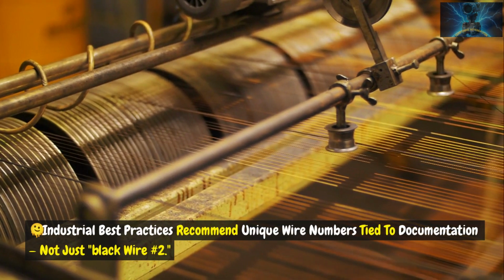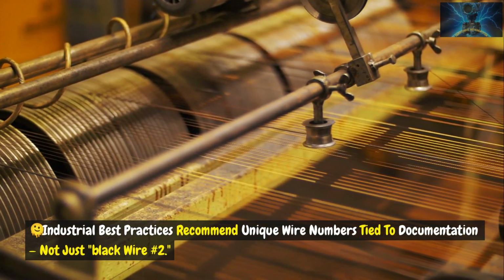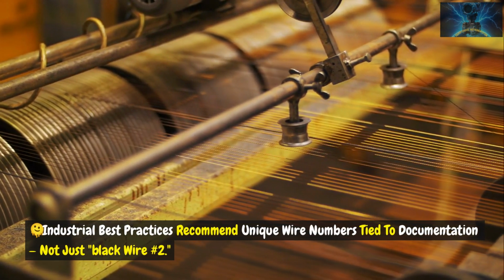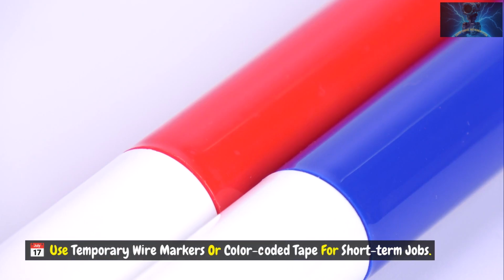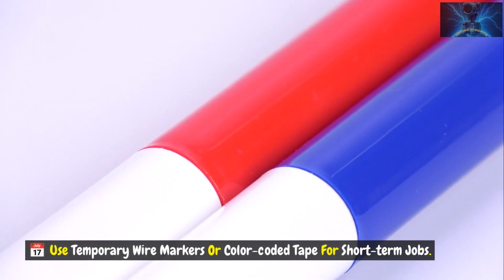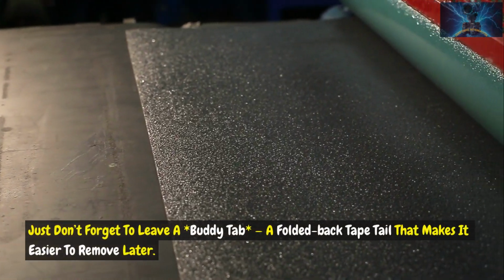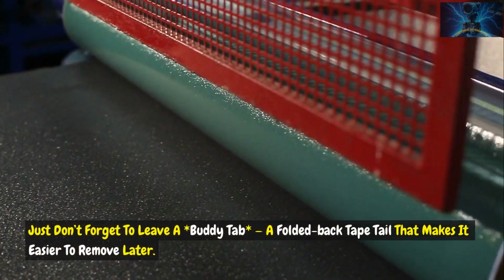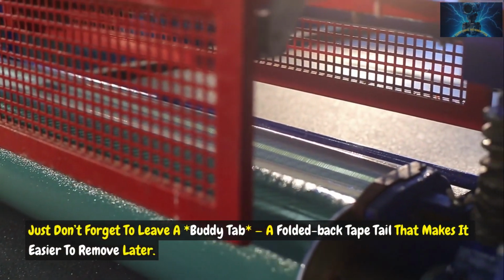Industrial best practices recommend unique wire numbers tied to documentation, not just black wire number 2. Use temporary wire markers or color-coded tape for short-term jobs. Just don't forget to leave a buddy tab, a folded-back tape tail that makes it easier to remove later.